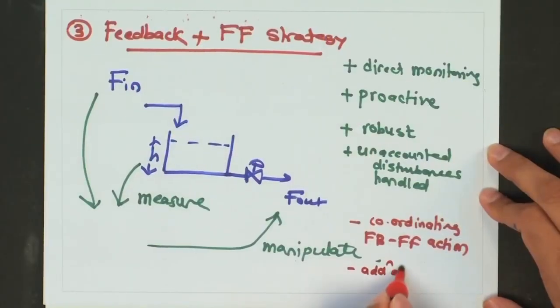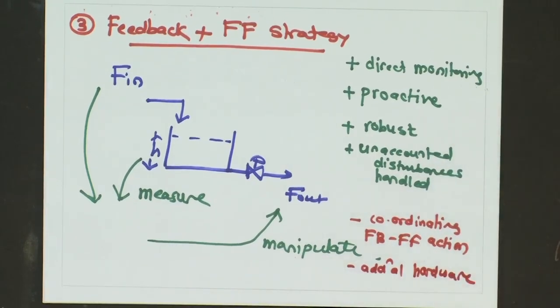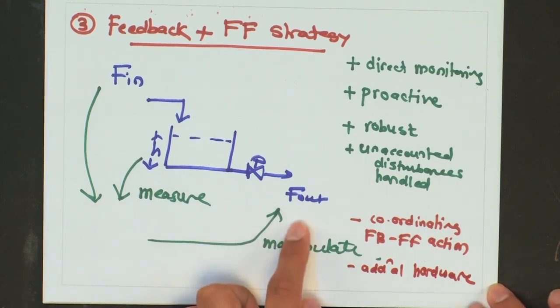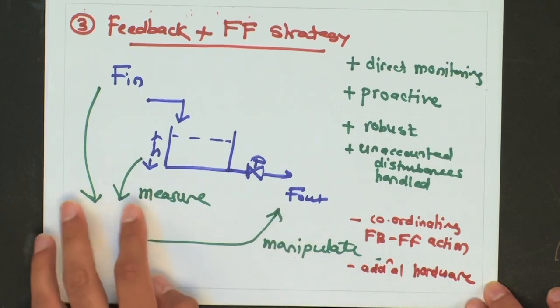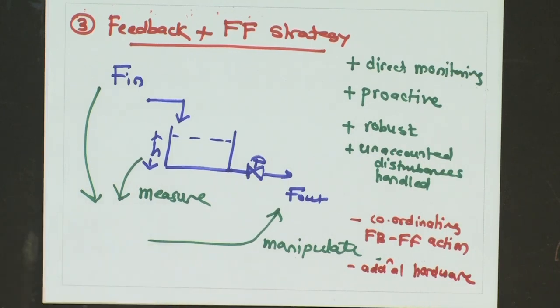There is also a limitation that you require additional hardware. In the typical feed forward or feedback strategy there is only one measurement and one control action. In this case there are two measurements which have to be made, so for every control loop there will be an additional cost of two instruments rather than one. But this is generally a secondary limitation — the major limitation is always maintaining coordination between these two control actions.